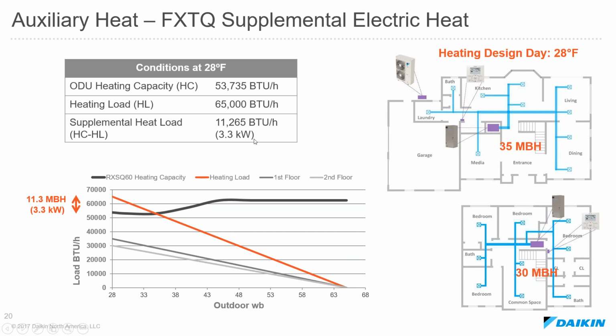It equates to around 11,000 BTUs an hour short, which is around 3.3 kilowatts. So it's pretty small. In this scenario, our only option really is to put a 3 kilowatt electric coil, because that's the smallest we have in each one of those units. But if it was larger and you needed to actually size electric heating, you could proportion that needed electric heat per the size of the indoor unit. We see that same balance point curve, but again, remember, we don't really need to calculate a balance point. This is going to come on automatically and help the unit when it sees it starting to struggle to meet that set point. But it can be useful to do something like this to get an idea of the gap between the capacity and the load.